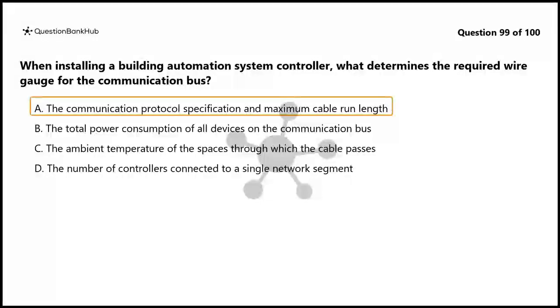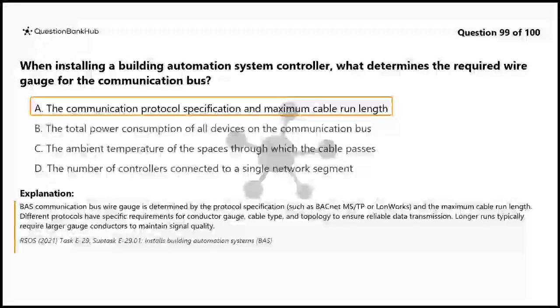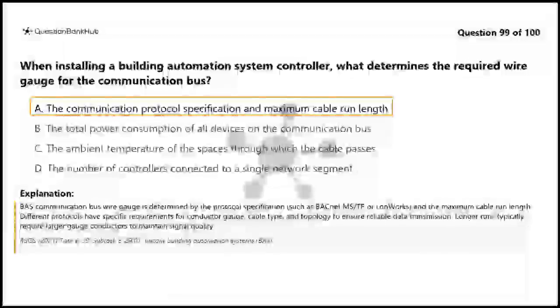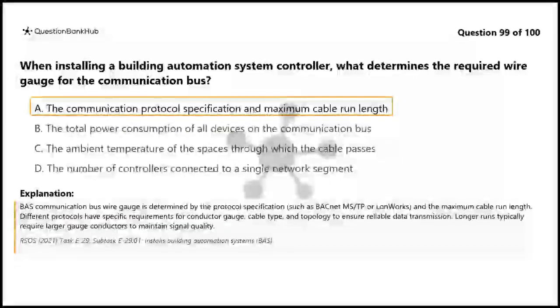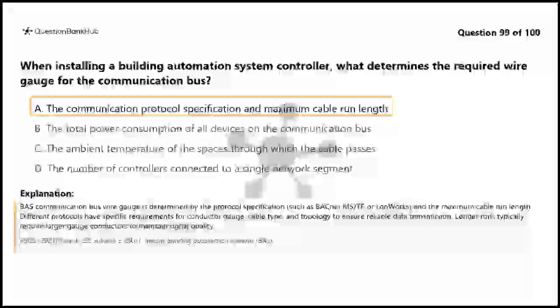The correct answer is A. The communication protocol specification and maximum cable run length. BAS communication bus wire gauge is determined by the protocol specification, such as BACnet MS/TP or LonWorks, and the maximum cable run length. Different protocols have specific requirements for conductor gauge, cable type, and topology to ensure reliable data transmission. Longer runs typically require larger gauge conductors to maintain signal quality.